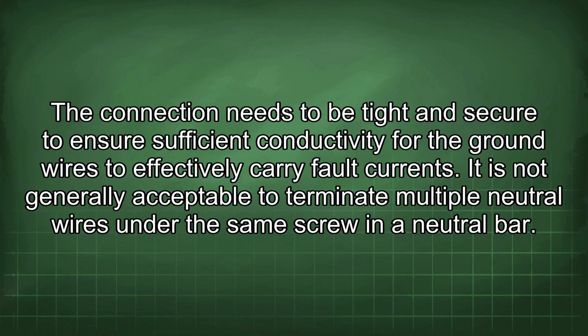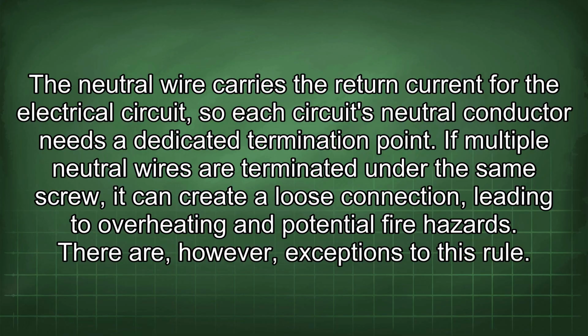carry fault currents. It is not generally acceptable to terminate multiple neutral wires under the same screw in a neutral bar. The neutral wire carries the return current for the electrical circuit, so each circuit's neutral conductor needs a dedicated termination point. If multiple neutral wires are terminated under the same screw, it can create a loose connection, leading to overheating and potential fire hazards.